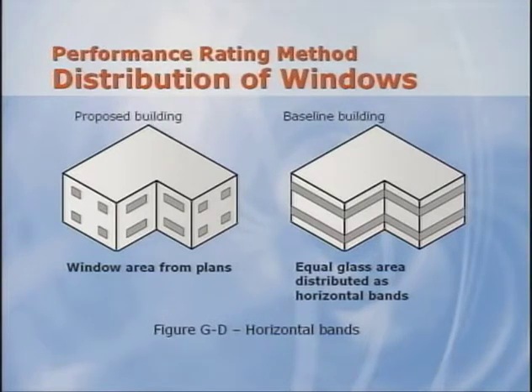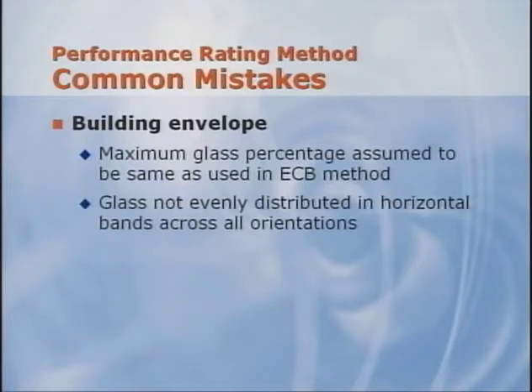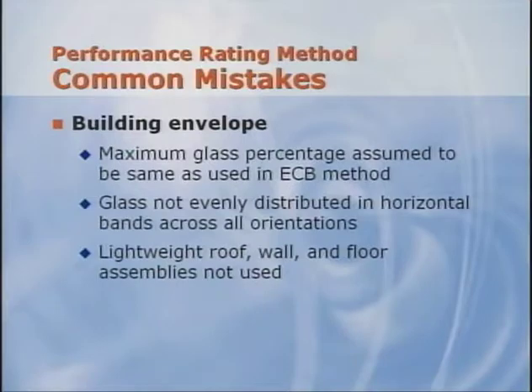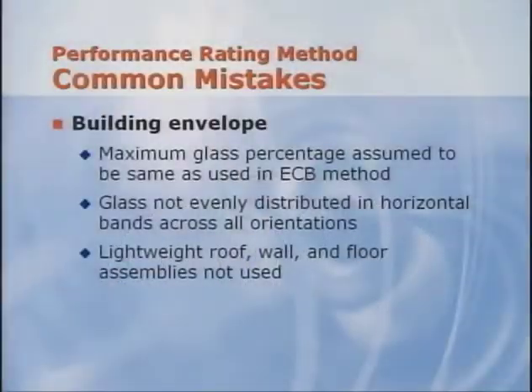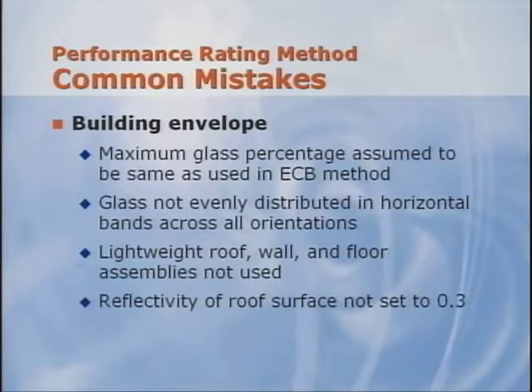This is often overlooked. Next, Appendix G directs you to model lightweight roof, wall, and floor assemblies in the baseline building. This means basically steel-framed walls and steel joist floors. Many energy modelers just use whatever was modeled in the proposed building. The final common error for the envelope is pretty obscure, but people often forget to set the reflectivity of the roof surface equal to 0.3. Next, I'll cover the common errors made when modeling HVAC systems using the performance rating method.